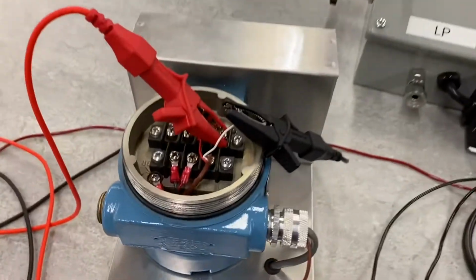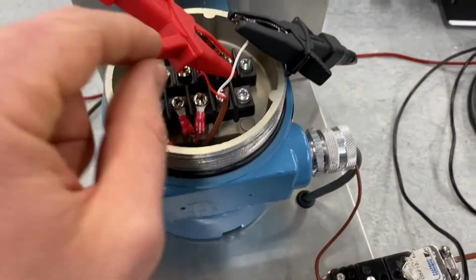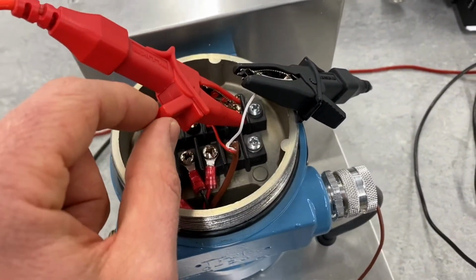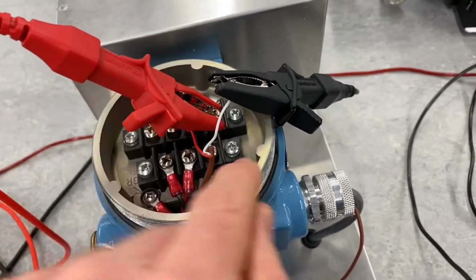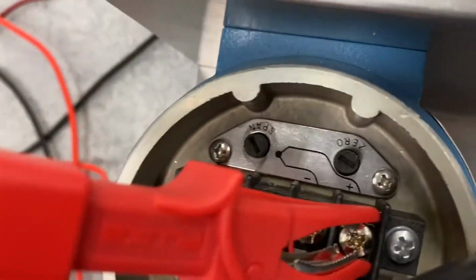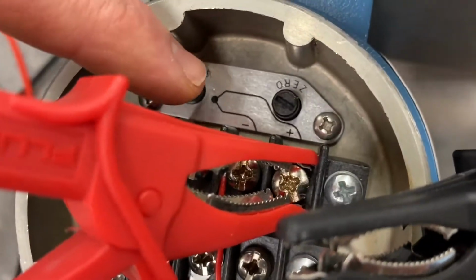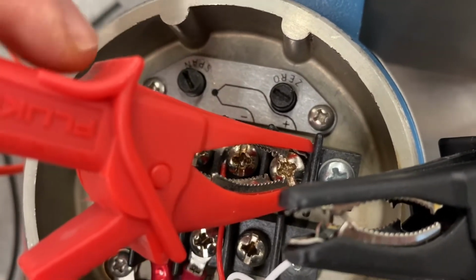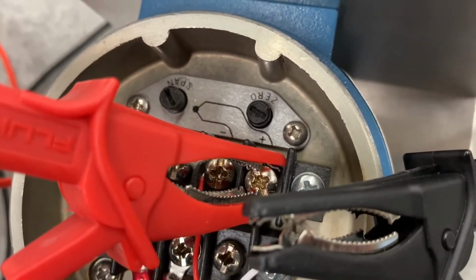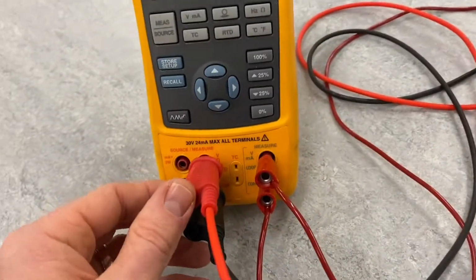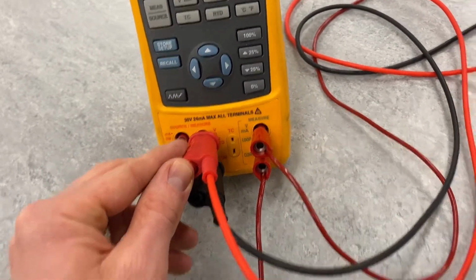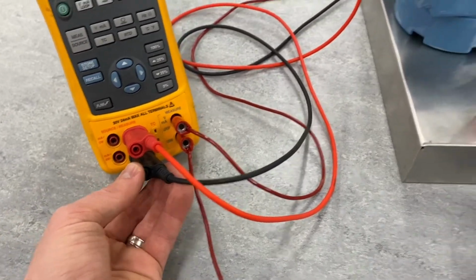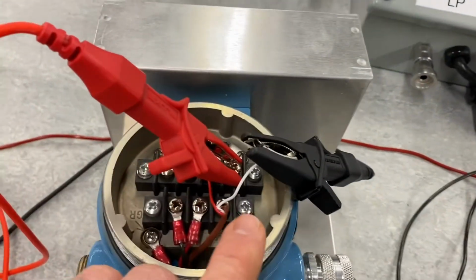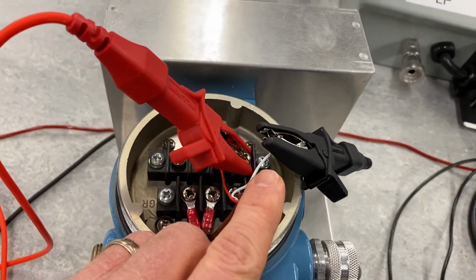Let's just see over here. You can see how I have the positive, this red alligator clip, connected to the positive. You can see the thermocouple diagram here on the transmitter. The red alligator clip is connected to the positive there, and then goes back over here to our meter, where we can source a millivolt value out. The negative side of our meter, this black lead, is connected to the negative lead on our thermocouple.